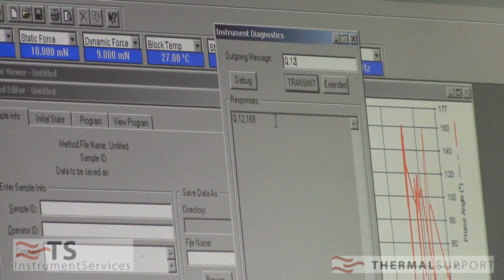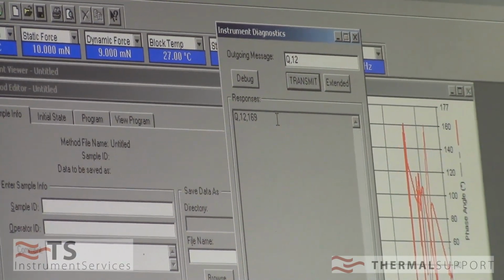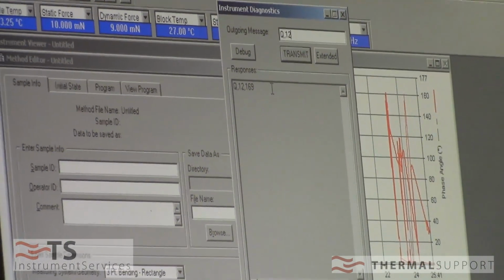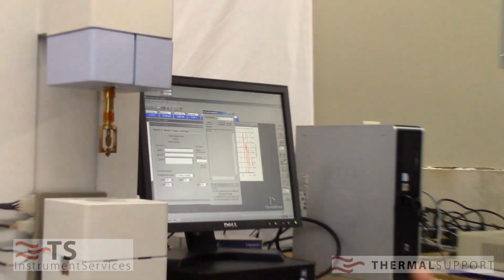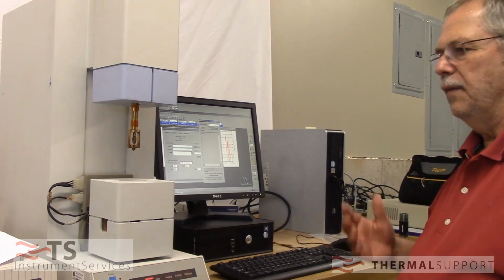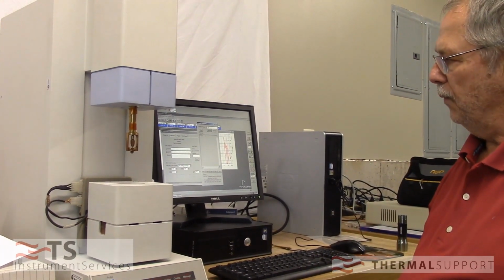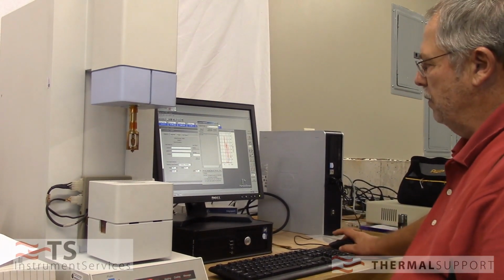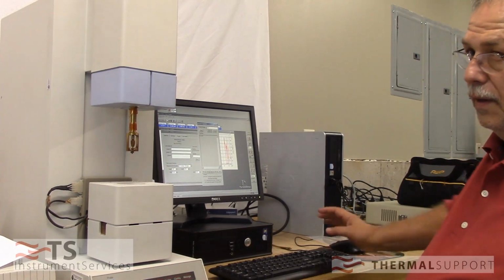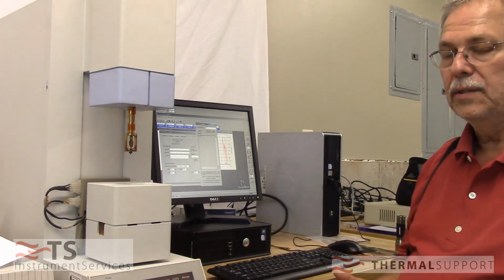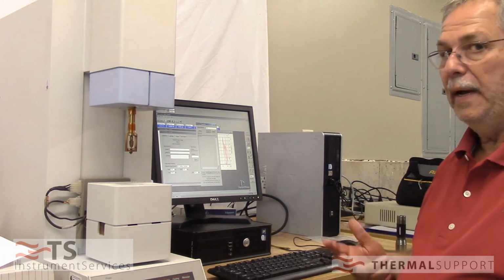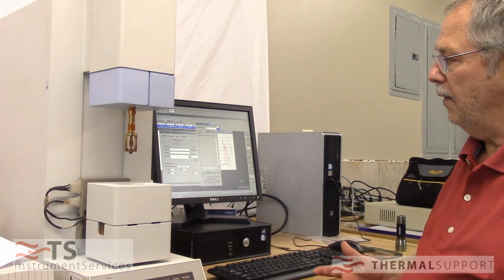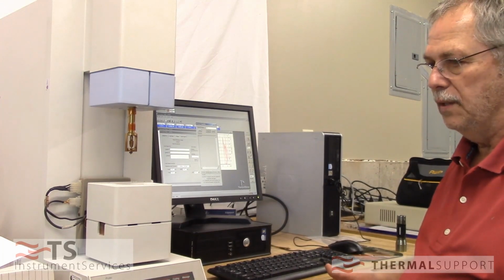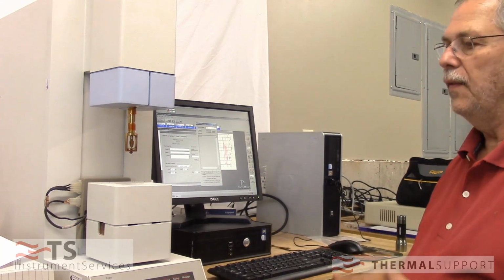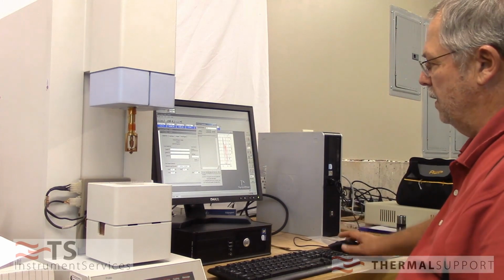We like it on the low end because it gives you a long way to go over the years, so that if you pick up any contamination from your laboratory environment, it's going to give you a pretty good while before you start going out of that range and start having any trouble. So what I'm going to do is close this out, and then we're going to go to the calibration screen, and we're going to start the DMA cal. Now when we start the DMA cal, it's a 30-minute calibration. So we're going to stop the video, and then we will restart when it's done to finish the calibration.